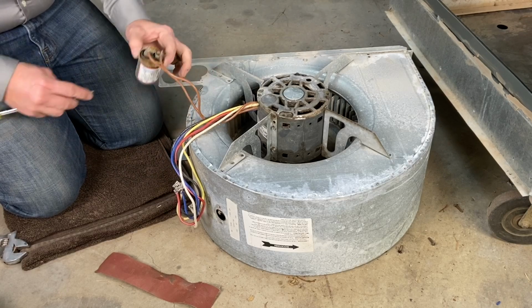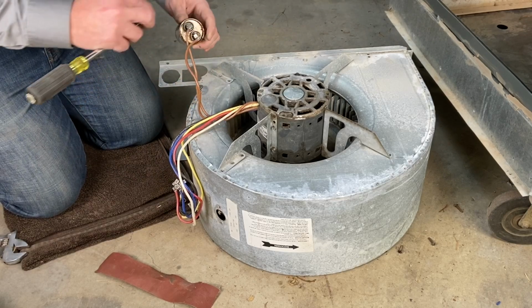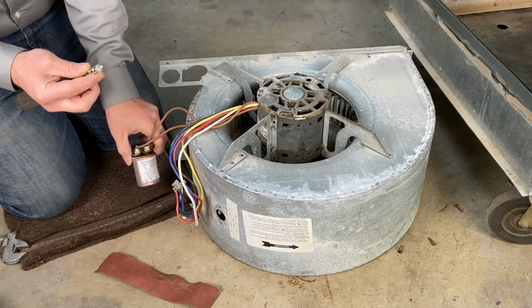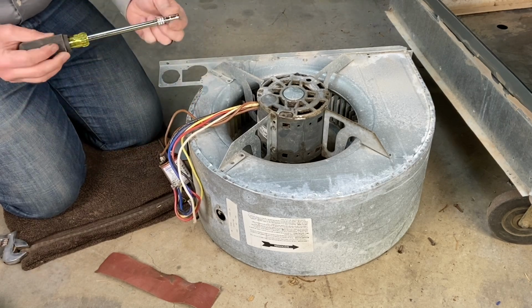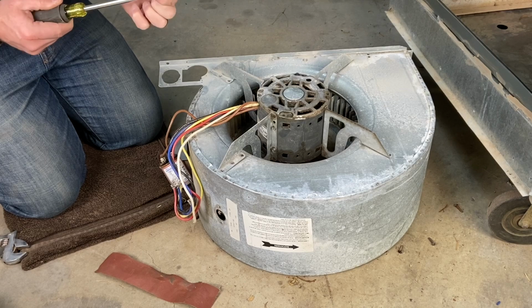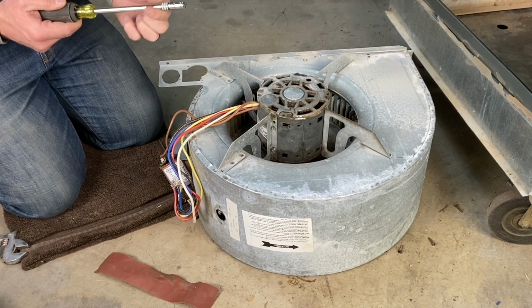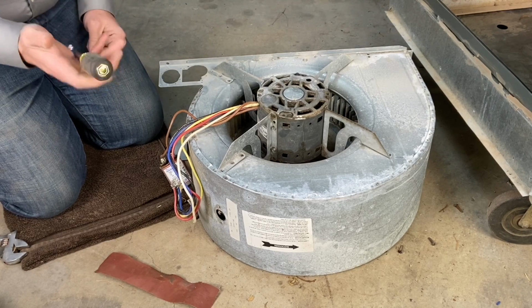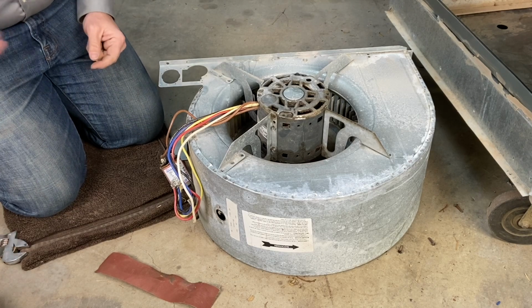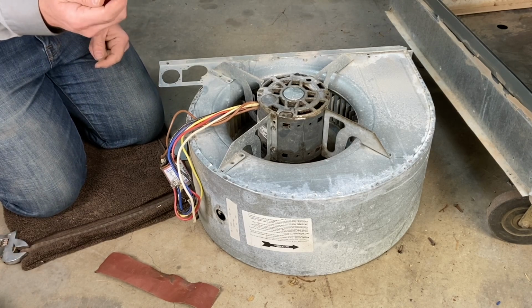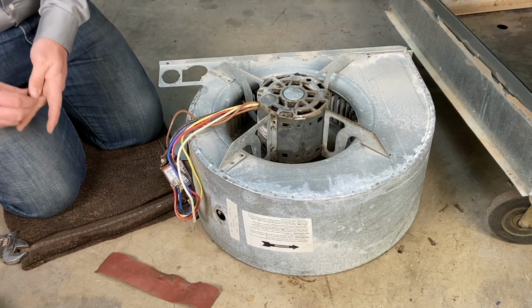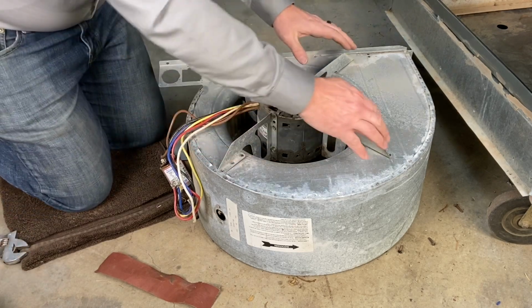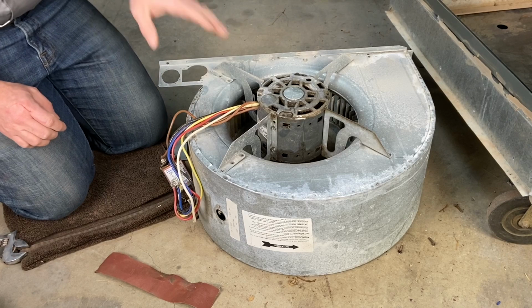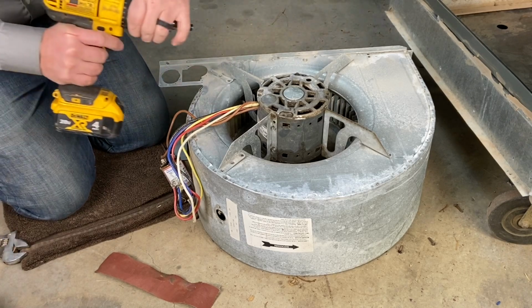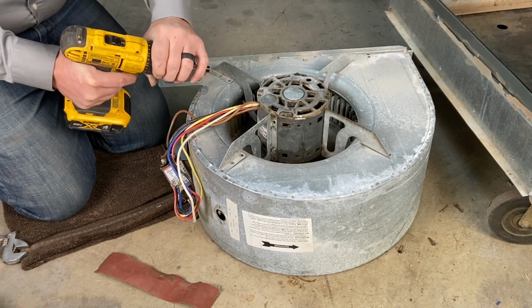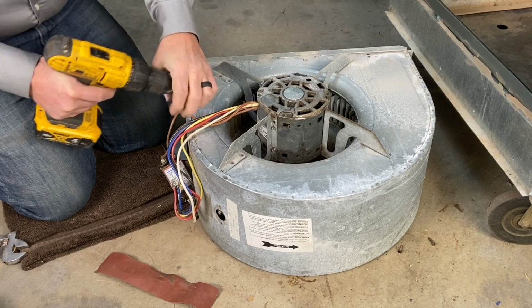Everything on this was a 1/4 inch except for this one screw that held our capacitor. This was a 5/16. One of the things that's nice is Klein makes this cool little screwdriver that has both sides to it, so it does 1/4 inch and 5/16. The only thing I don't like is it's just too heavy, so I fall back to my old lightweight nut driver. I've had this one for probably 25 years. There's tons of stuff out there. I did use a drill for this because it takes it loose very quickly. If you're putting screws back together, you want to make sure you use the torque setting on your drill so that you don't over tighten those screws.